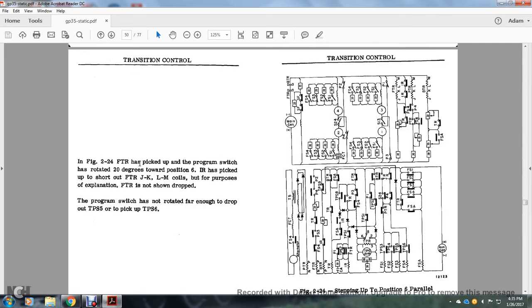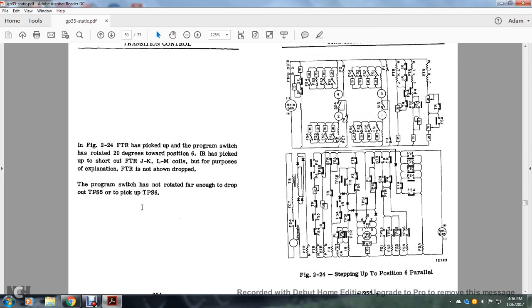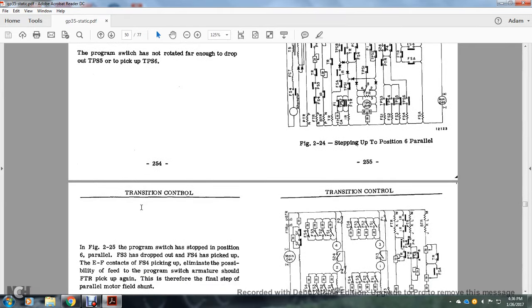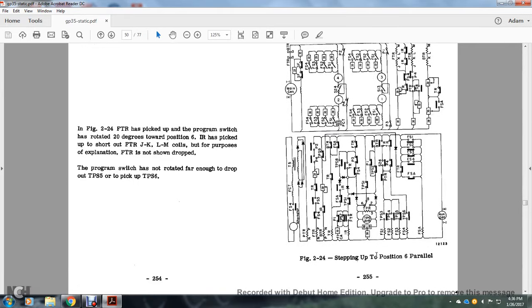In figure 24, the field shunt transition relay is picked up and the program switch has rotated 20 degrees to position 6. The interrupting relay is picked up, shorting the front transition relay JK and LM. For the purpose of explanation, the front transition relay is not shown dropped. The program switch has not rotated far enough to drop transition parallel switch 5 to transition power pickup or to pick up transition parallel switch 6. Alright, figure 24 shows the stepping up to position 6 parallel.